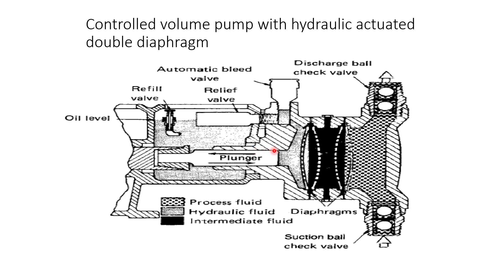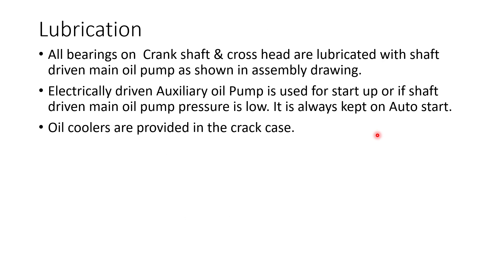In this slide, we can see a double diaphragm pump, called a controlled volume pump with hydraulic actuated double diaphragm. Sometimes when handling certain corrosive or toxic fluids, if they leak there can be a very big hazard. In that case, we use two diaphragms — one diaphragm here and a second diaphragm — with oil filled between the two diaphragms. The plunger pushes the oil and the oil pushes the diaphragm. When pushed to the right, the discharge valve opens and liquid gets discharged. When it moves to the left, the suction valve opens and the cavity gets filled.